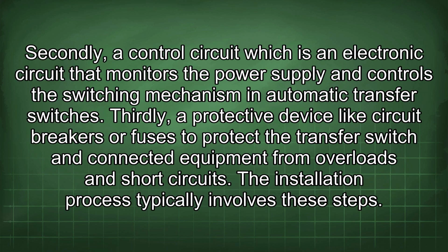Secondly, a control circuit, which is an electronic circuit that monitors the power supply and controls the switching mechanism in automatic transfer switches. Thirdly, a protective device like circuit breakers or fuses to protect the transfer switch and connected equipment from overloads and short circuits.